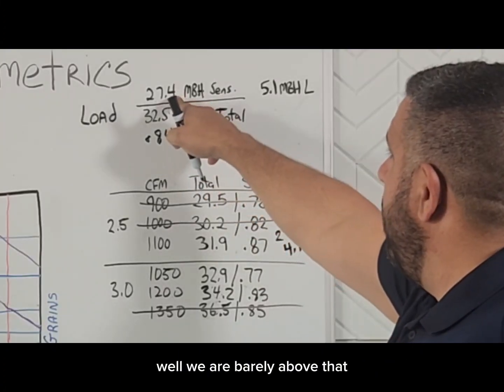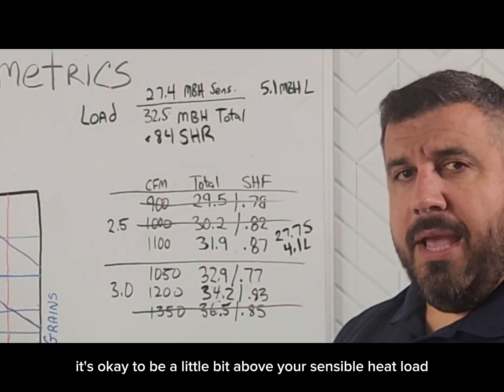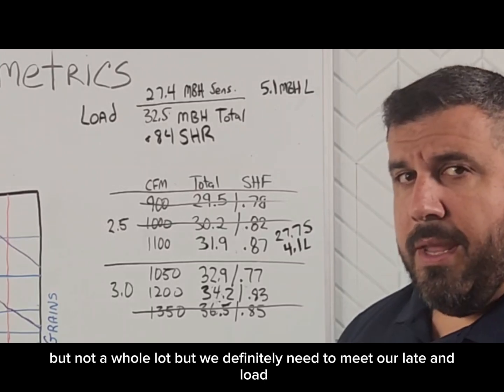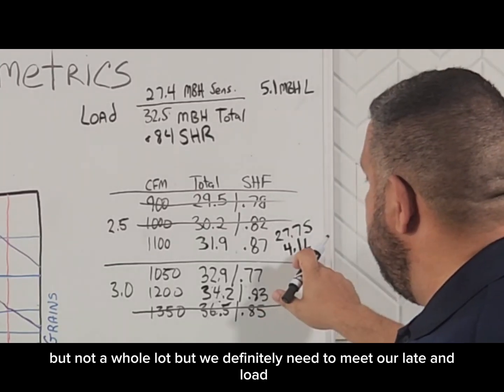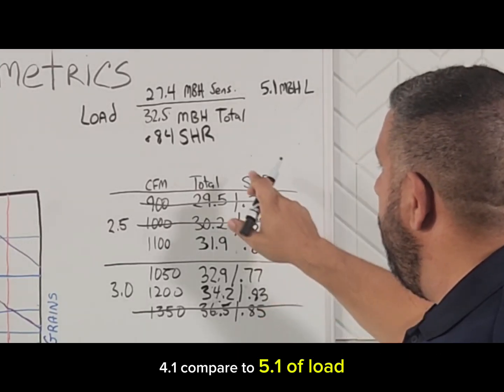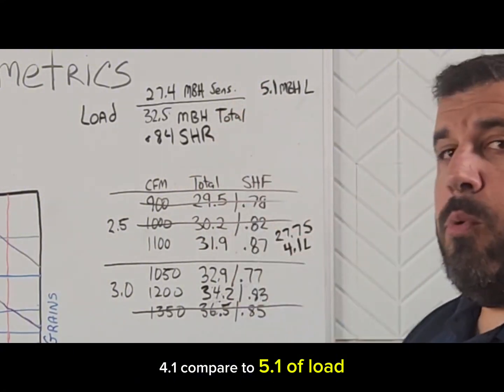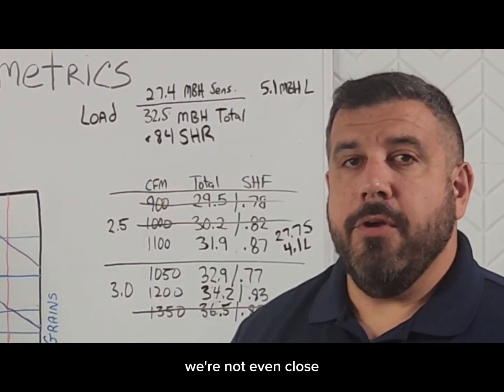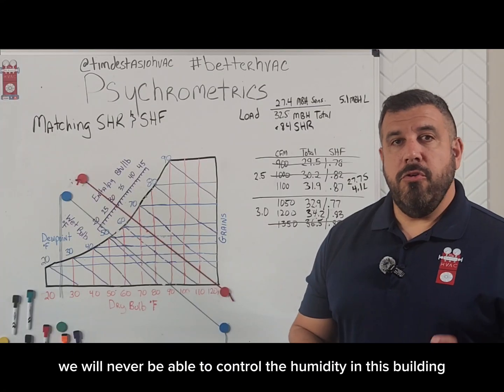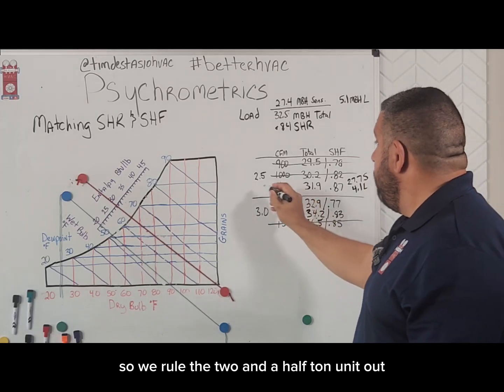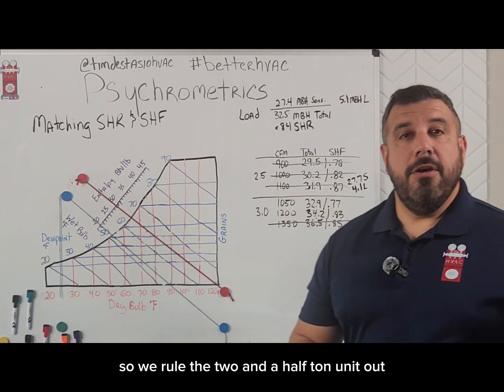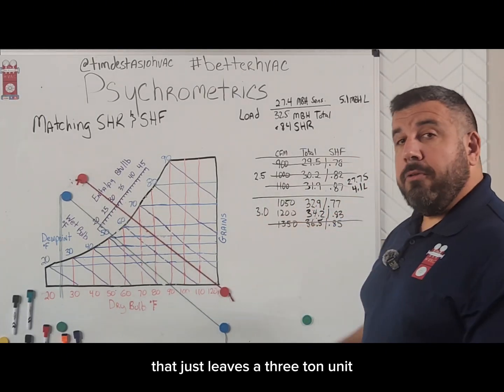Let's compare that to our load. 27.7 sensible. Well, we are barely above that. It's okay to be a little bit above your sensible heat load, but not a whole lot. But we definitely need to meet our latent load. 4.1 compared to 5.1 of load, we're not even close. We will never be able to control the humidity in this building. So we rule the 2.5 ton unit out. That just leaves a 3 ton unit.